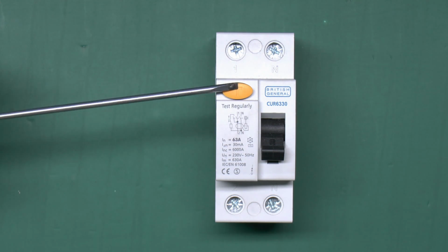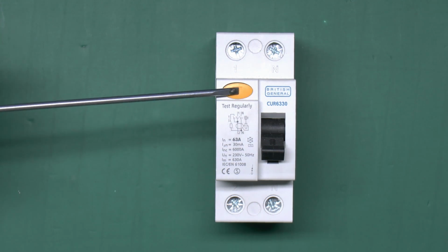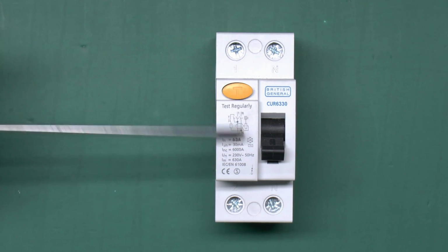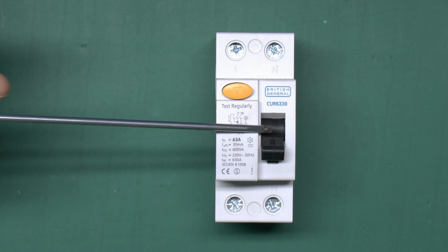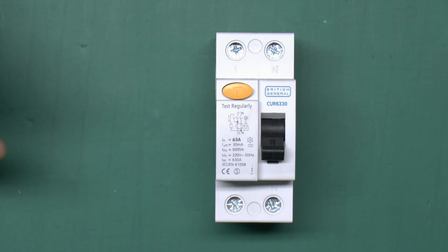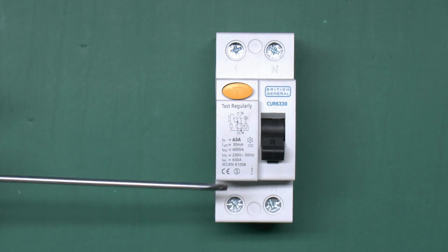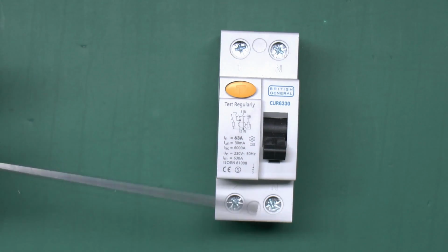Now all of these have a test button on which basically simulates an imbalance in the current. That's just to make sure that the thing will trip, and if you press the button and it doesn't trip, then of course that would indicate a fault with the device and it would need to be replaced. Now this is a single phase device, it's just got the single line on this side and the neutral here.